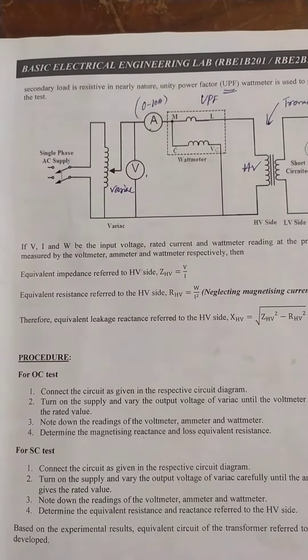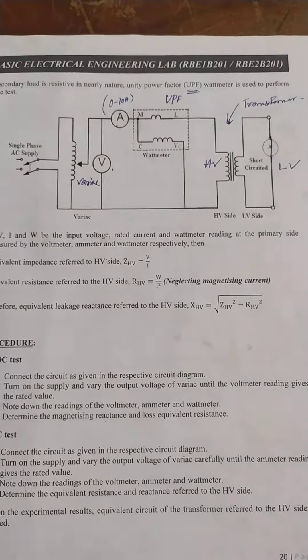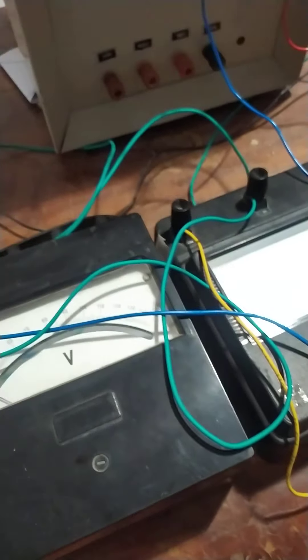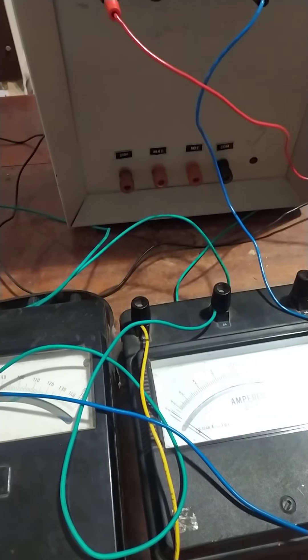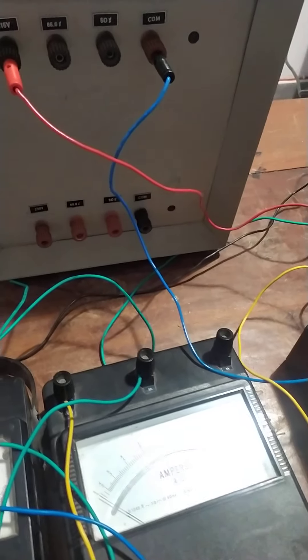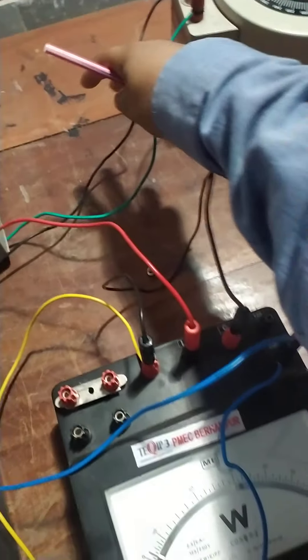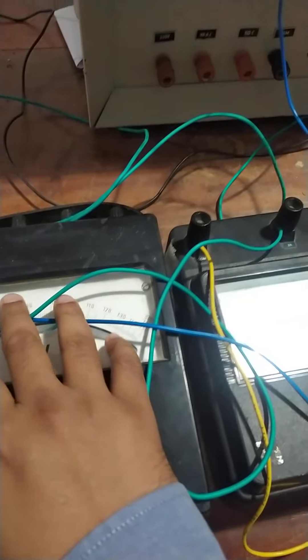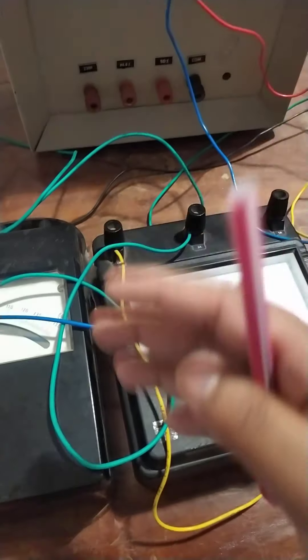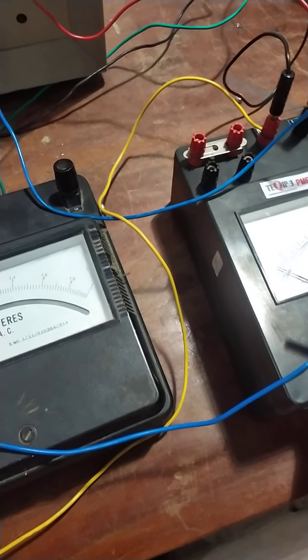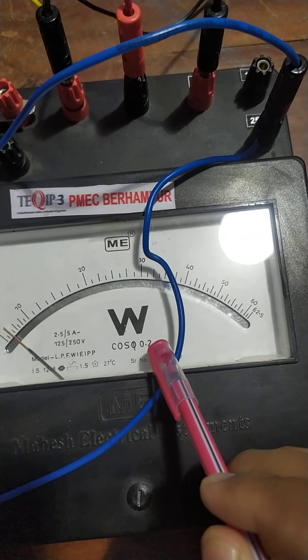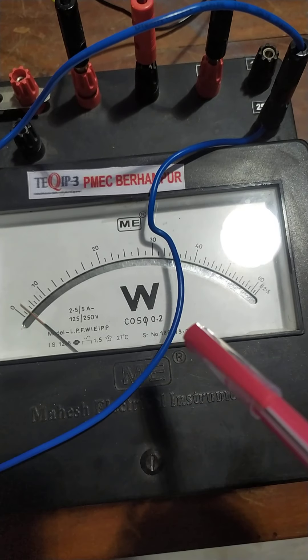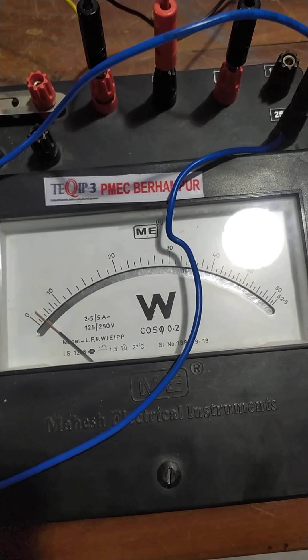The setup is ready for the open circuit test. We have kept the high voltage side open and connected the setup on the low voltage side. From the variac it goes to the voltmeter, then to the ammeter and wattmeter. You can see the wattmeter is marked with cos φ equal to 0.2, which confirms this is a low power factor wattmeter.